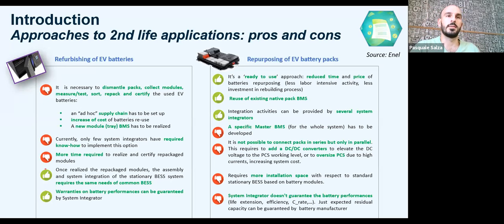On the contrary, there are other limitations that can be overcome, and we will see how. First, you need a higher level control system, a so-called master BMS, to communicate with the single BMS of the packs, managing all these battery packs that weren't meant to work together, and to communicate with the overall power conversion system that connects the battery packs to the grid.